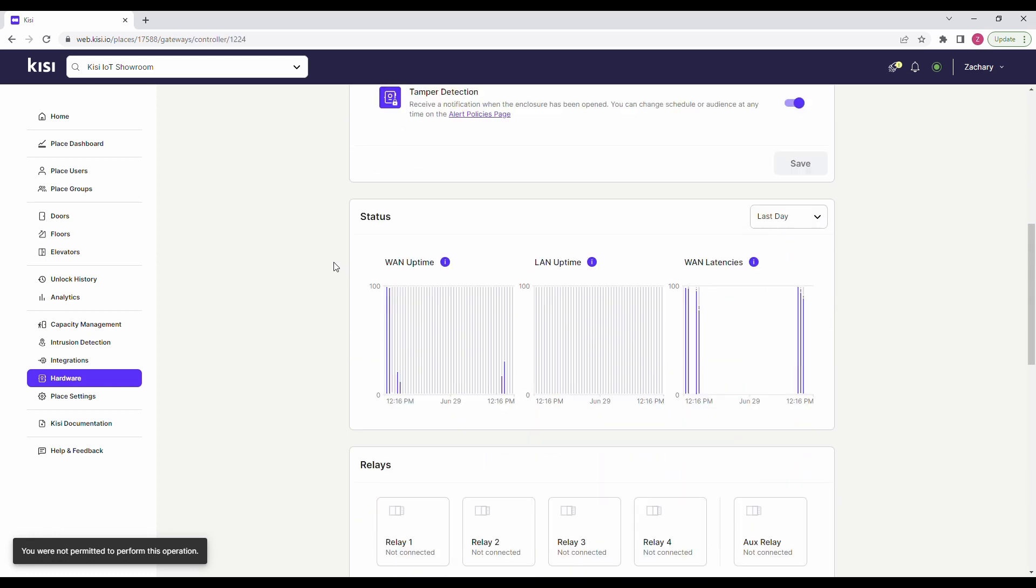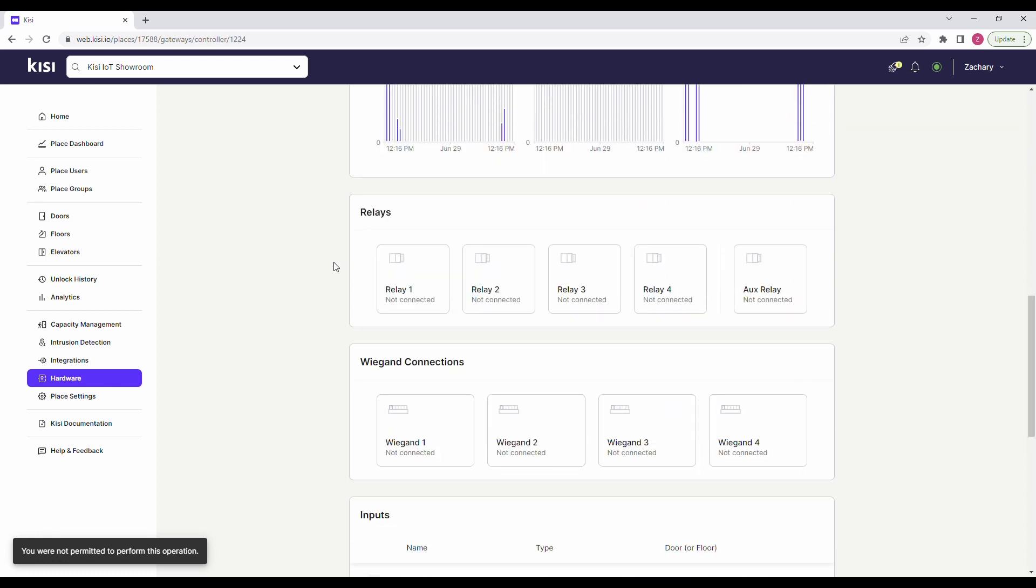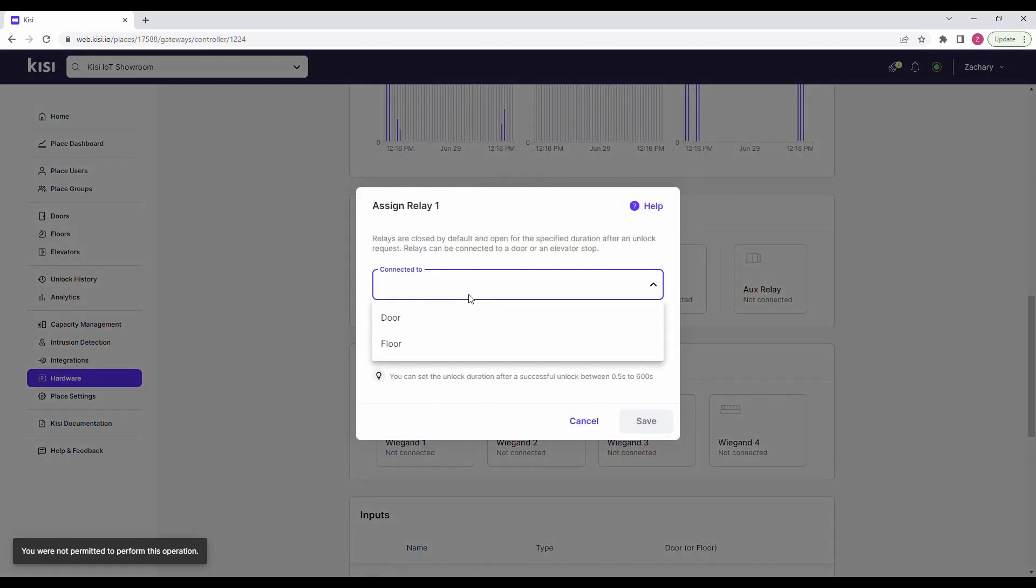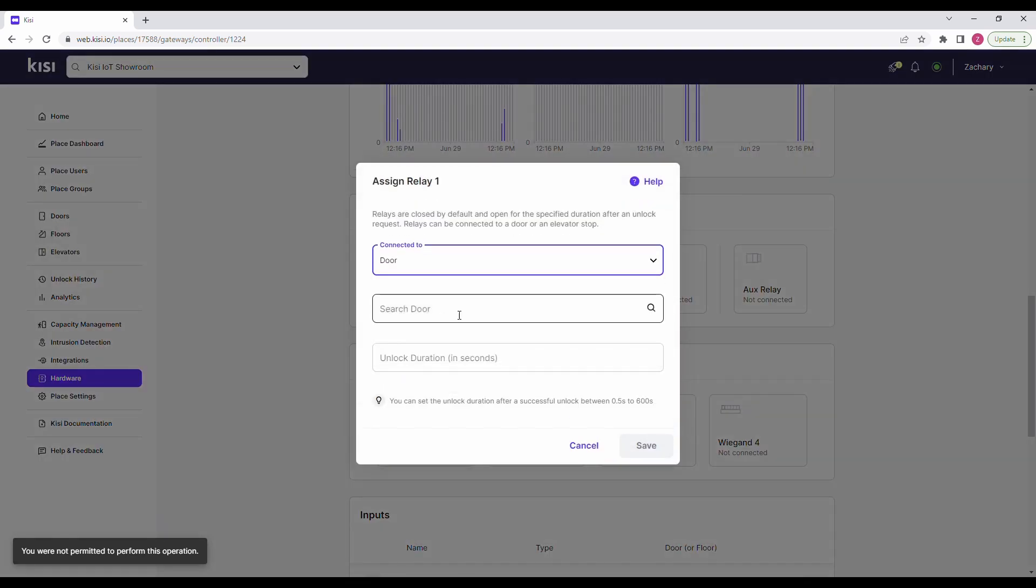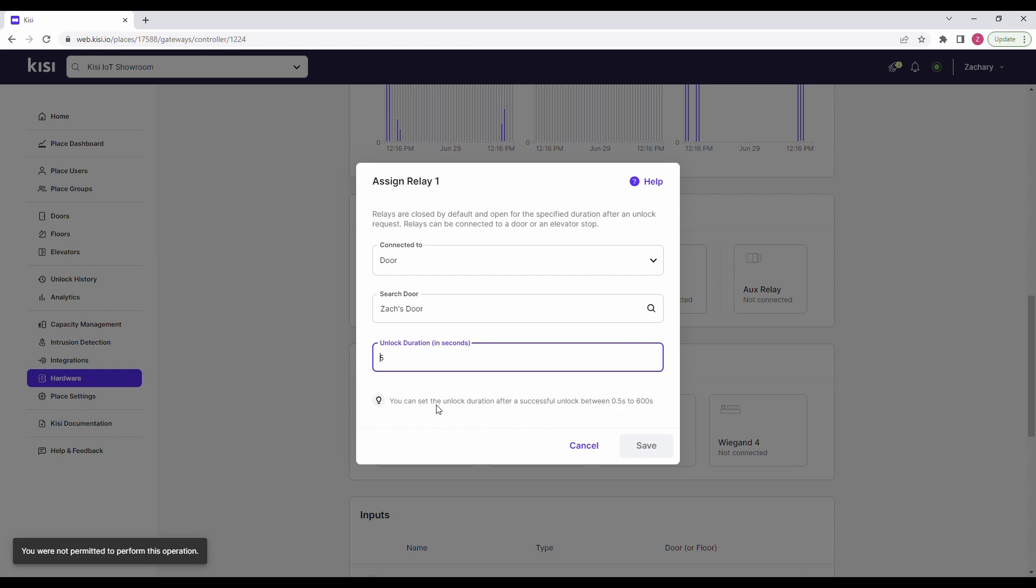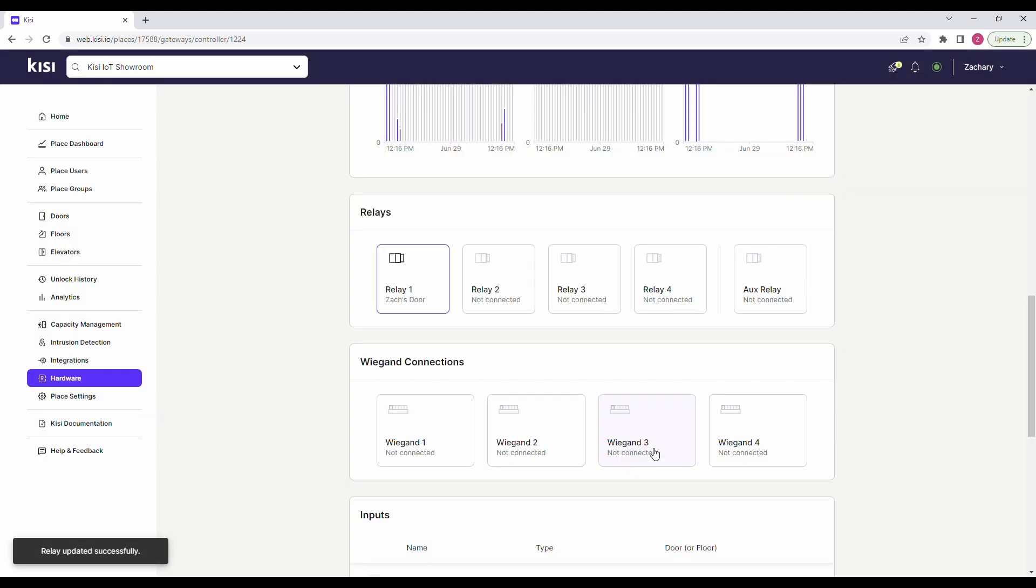Scroll down and choose the relay channel that corresponds to the maglock that has been connected to the system. Click on Search Door or Elevator and enter the door that is being secured by the maglock. Click on Unlock Duration and select how long you would like the door to remain unlocked after credentials are presented. Click on Save.